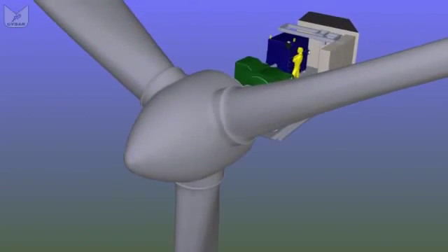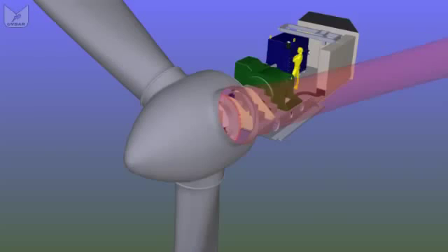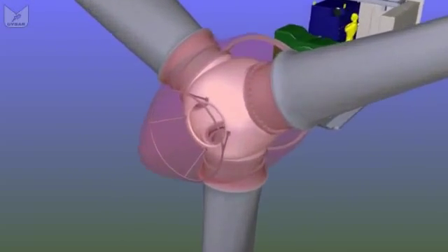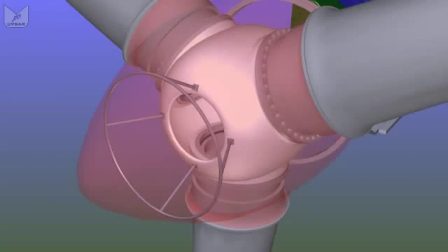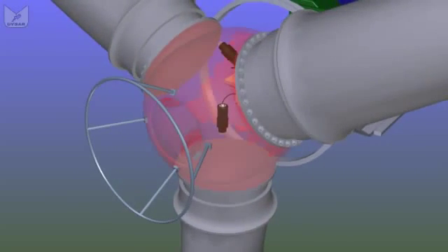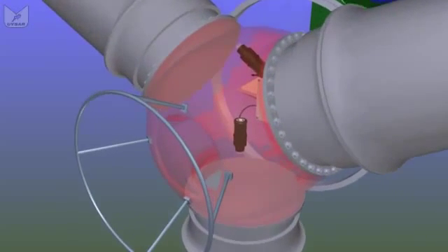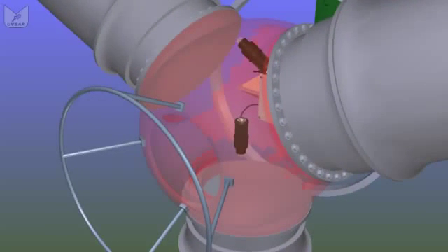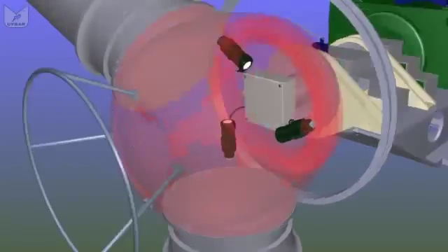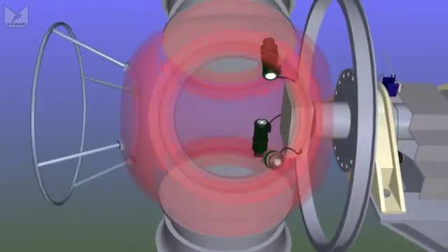We still have 3 of them. They still pitch, in other words, they twist on themselves to line up with the wind. And you access the hub through the gap between this fiberglass cowl and the cast hub. It's a bit of a wriggle, but you wriggle through, usually feet first, crawl through the hole in the middle of the hub, and inside the hub we'll find the control electronics, the pumps, the motors and the batteries to control the pitch of each blade, rotating it on its own bearing to set the optimum angle for the wind.